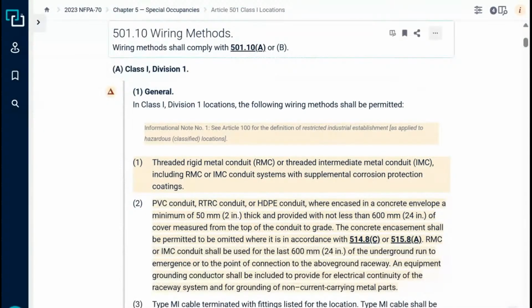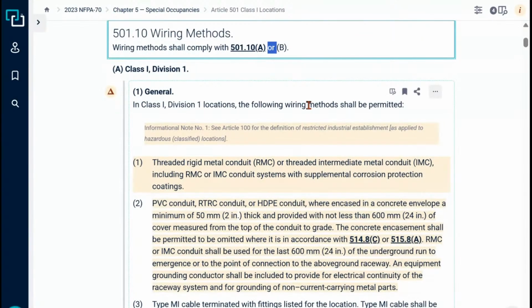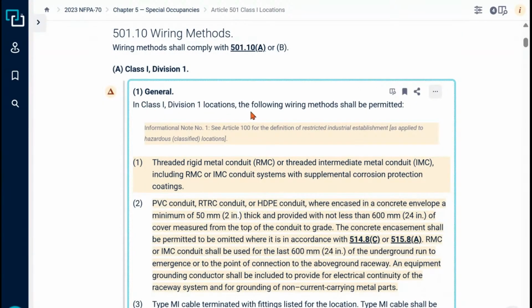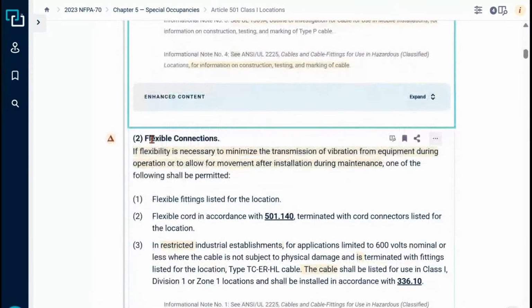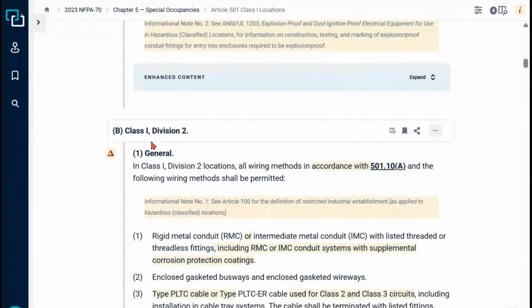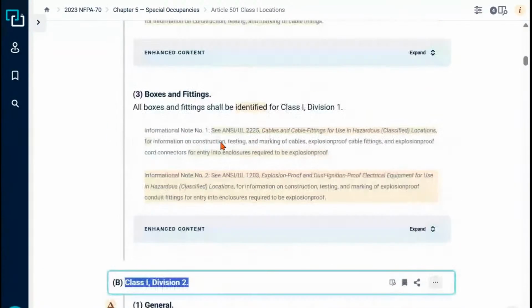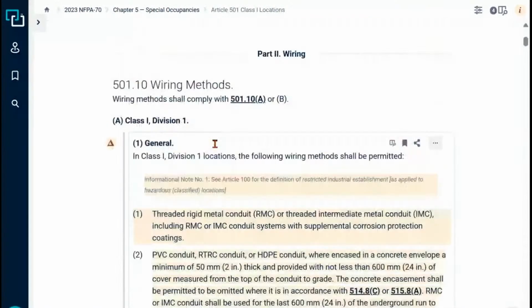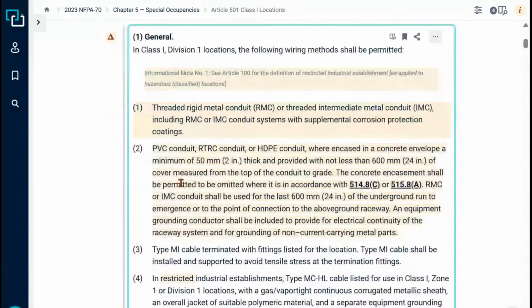So we're talking wiring methods, right? Shall comply with 501.10A, or, that's the power of or, folks. Y'all remember A or B as applicable. A is general. It says in Class 1 Division 1 locations, the following wire methods shall be permitted. It's permissive. I mean, I could go and use B if it's a Class 1 Division 2, but I'm permitted to use any of these applications depending on what it is.